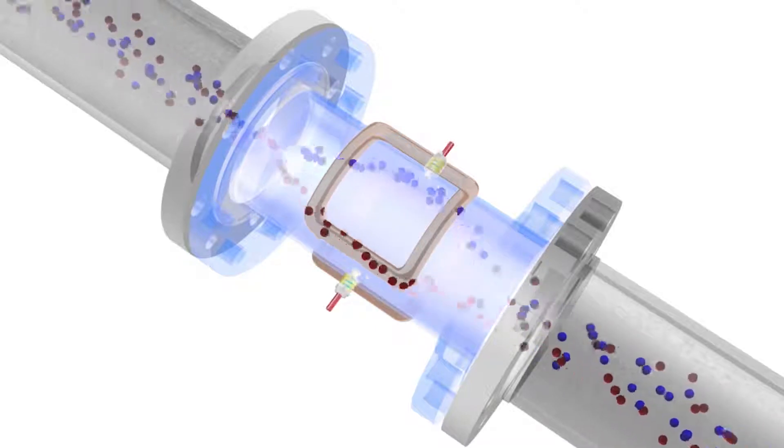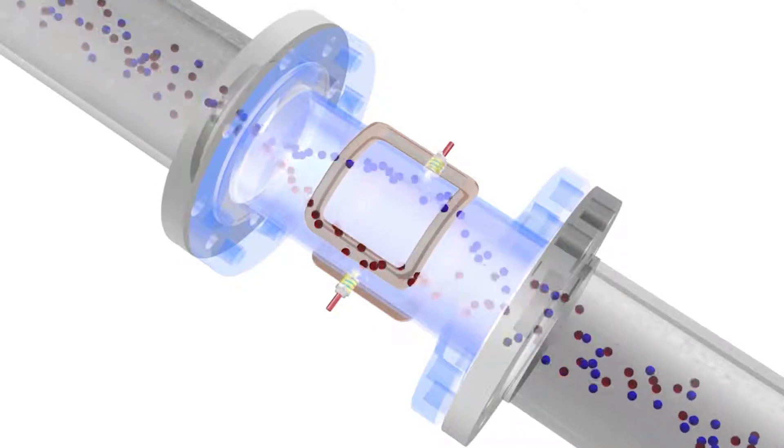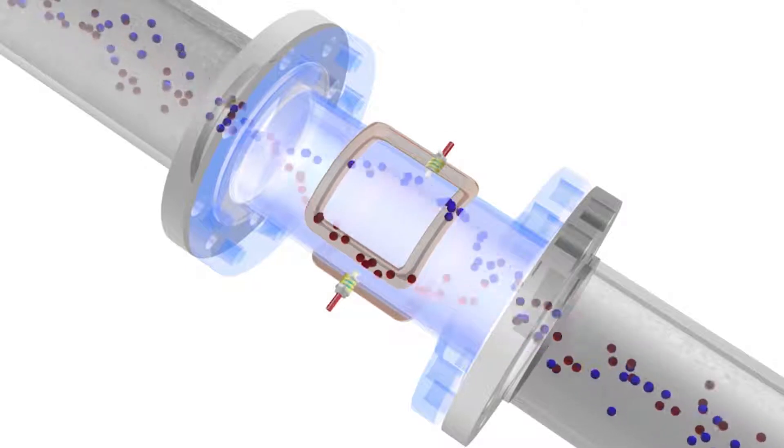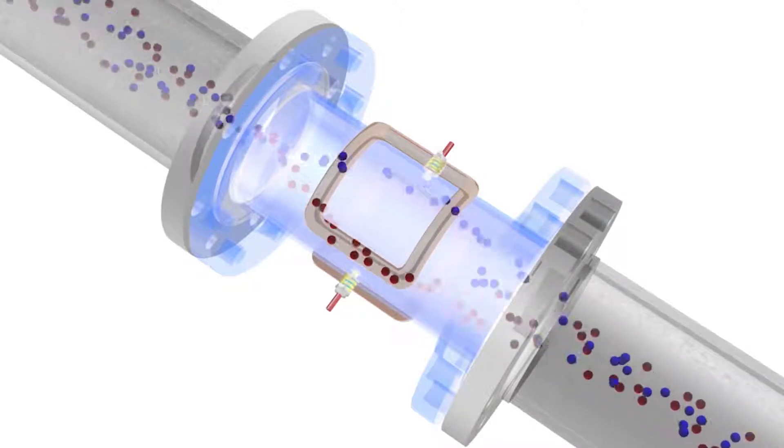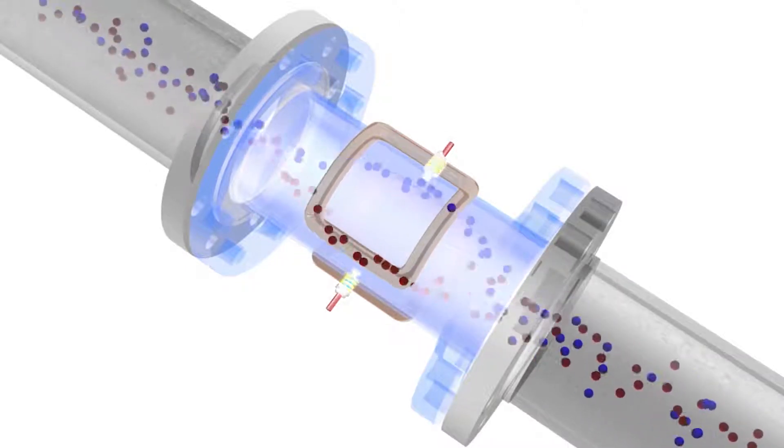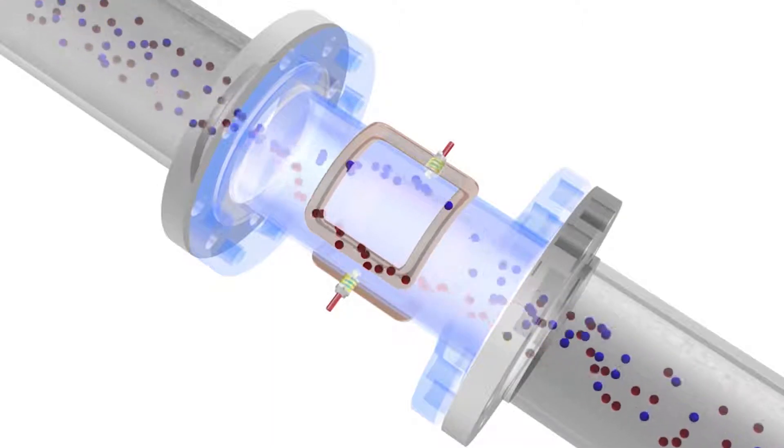This separation causes an induced voltage to be formed between the electrodes in the sensor. The conductivity or charge of the fluid in the pipe must be at a certain level for the transmitter to measure the induced voltage at the electrodes.